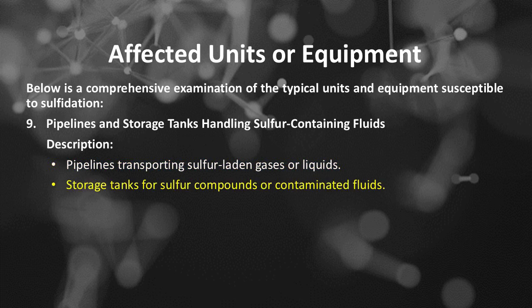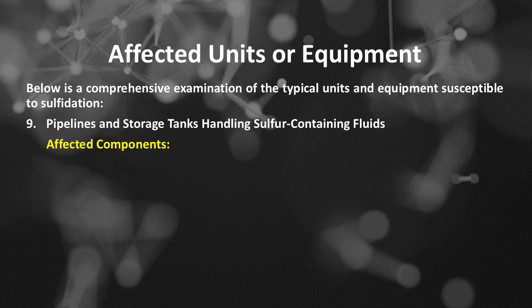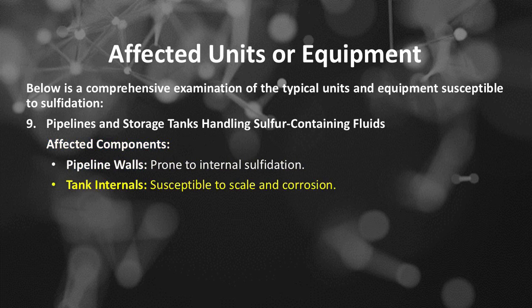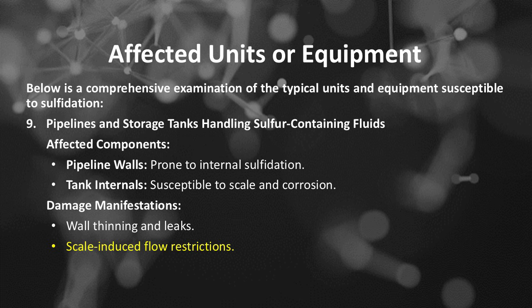Storage tanks for sulfur compounds or contaminated fluids. Pipelines and storage tanks handling sulfur-containing fluids. Affected components: pipeline walls, prone to internal sulfidation, and tank internals, susceptible to scale and corrosion. Damage manifestations: wall thinning and leaks, scale-induced flow restrictions, and structural failure due to embrittlement.